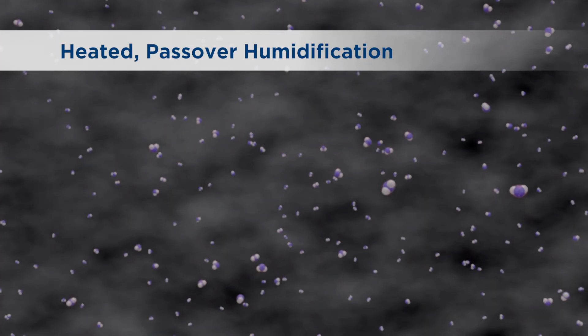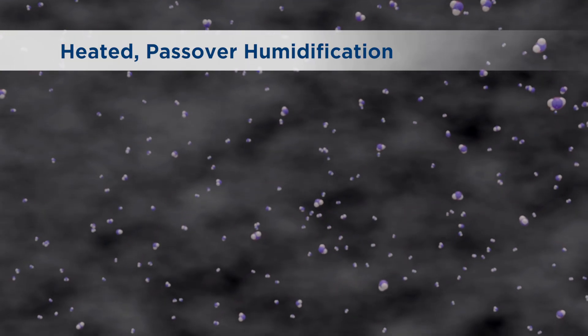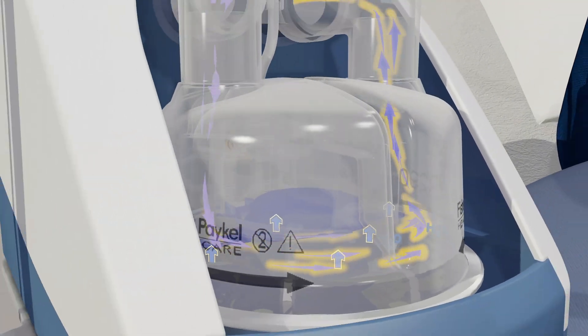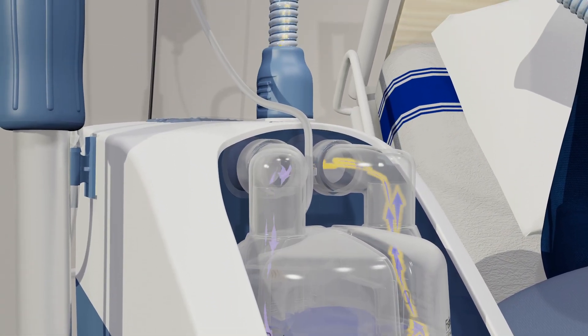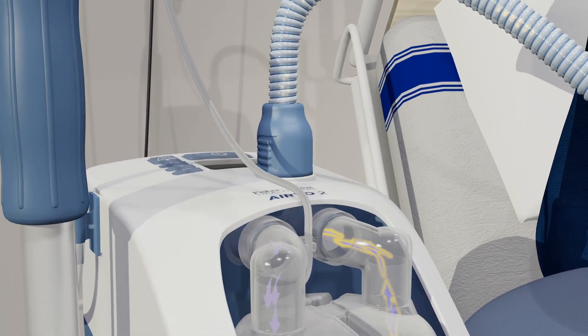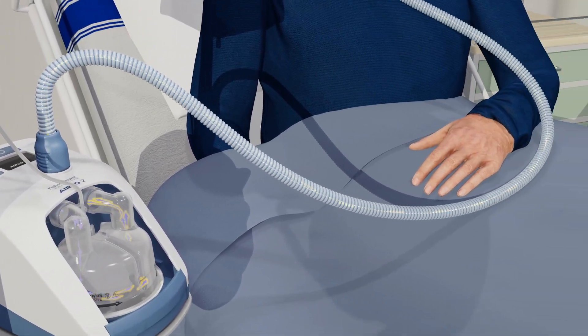So, by using water vapour for humidification instead of water droplets, the Airvo 2 can reduce the risk of infection. This water vapour, from the headspace in the water chamber, enters the breathing tube through the port on the top of the Airvo 2.